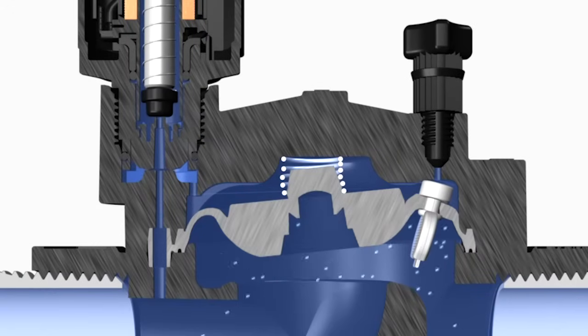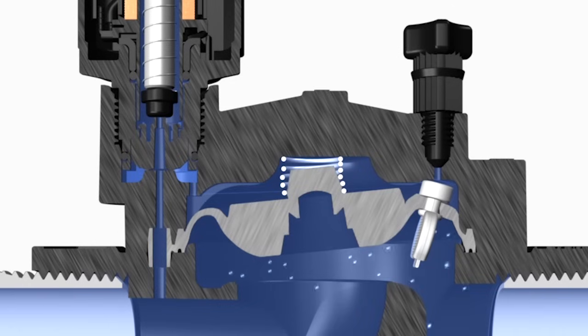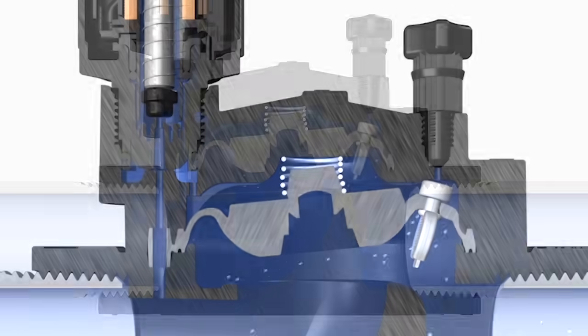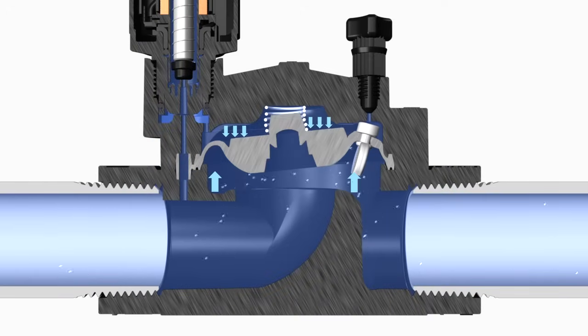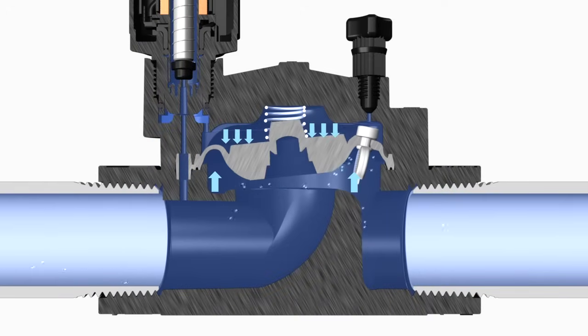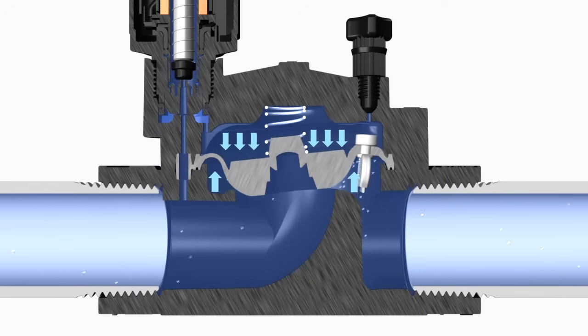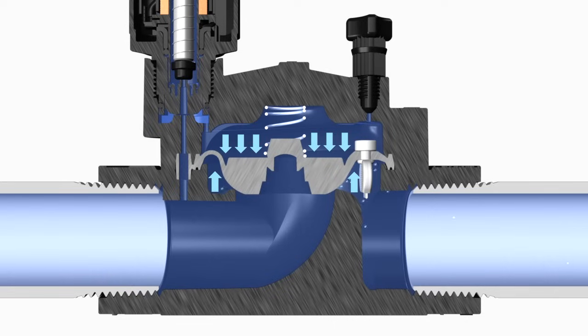the plunger drops inside the solenoid, and the water stops flowing in the solenoid dump port. Eventually, the bonnet chamber water pressure becomes high enough to offset the water pressure below the diaphragm, and the valve closes.